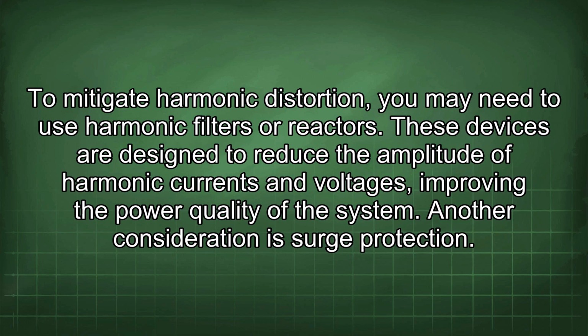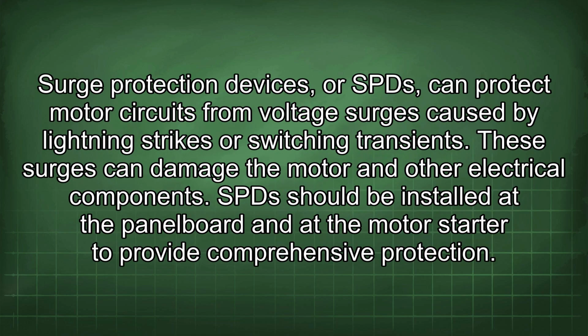Another consideration is surge protection. Surge protection devices, or SPDs, can protect motor circuits from voltage surges caused by lightning strikes or switching transients. These surges can damage the motor and other electrical components. SPDs should be installed at the panel board and at the motor starter to provide comprehensive protection.